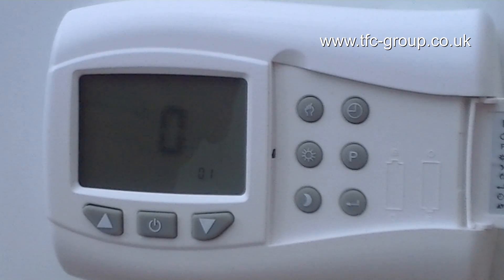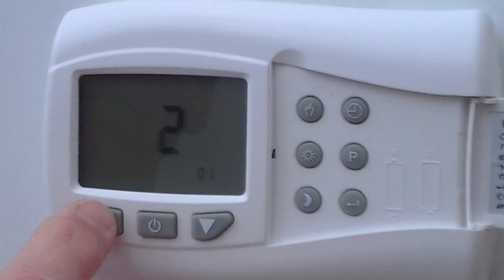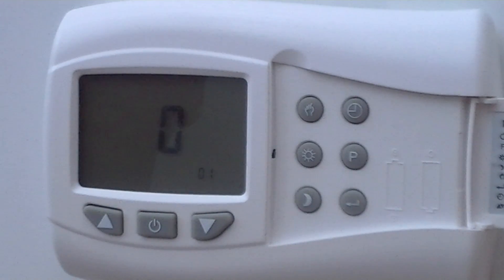The first option is a temperature adjustment to change the displayed temperature compared to the measured temperature. So if you think the unit is reading high or low, you can make an adjustment to increase or decrease the level displayed. The unit is calibrated for accurate temperature display, but you might need to make an adjustment if the individual installation has a drafty situation or some other impact which changes the way the temperature is displayed.